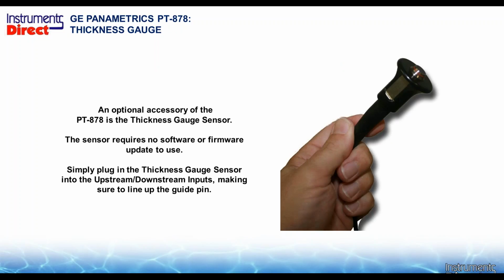Now, the thickness gauge. The thickness gauge is an option. Some people use it, some people don't. Let's get down to the reality factor of the thickness gauge. What is it measuring? A thickness gauge is designed to monitor and measure your continuous measurement from the top of the pipe to the inside of the pipe, as long as it's a metallic material.